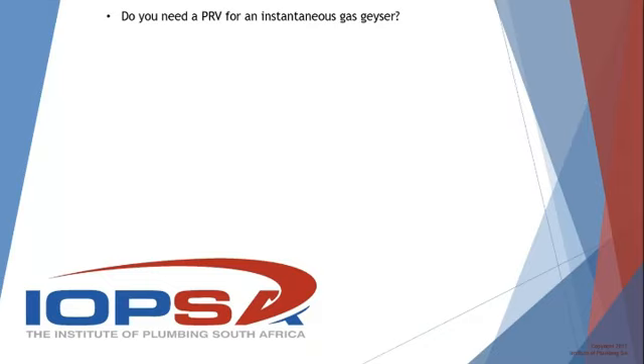Okay, morning guys. The question is straightforward. The requirement for a PRV: if you look at the rating on these instantaneous gas geysers, some of them can handle a higher rating, being non-storage. It's more of a pipe being heated than an actual cylinder. But the question shouldn't be around the PRV. There are two references to the water into a property. The one says that you can only have a maximum of 600 kPa. So whether the manufacturer in their little booklet tells you they can go 800 or 1000 kPa is beside the point. The standard says you can only have 600 kPa going into a building.